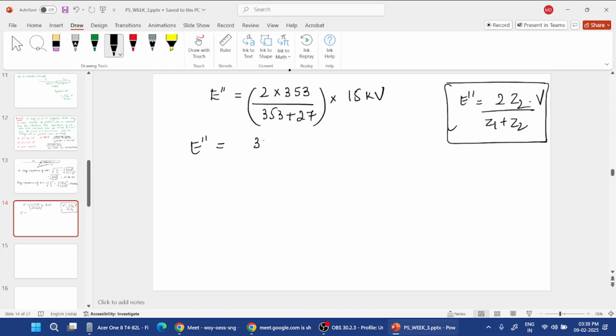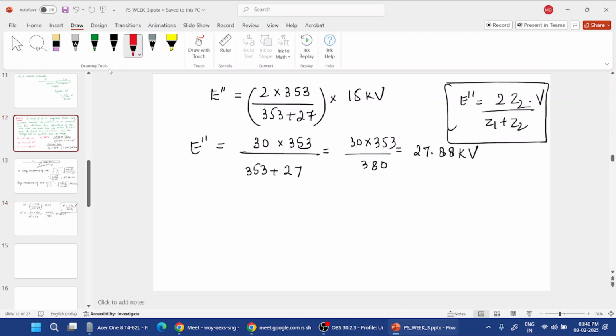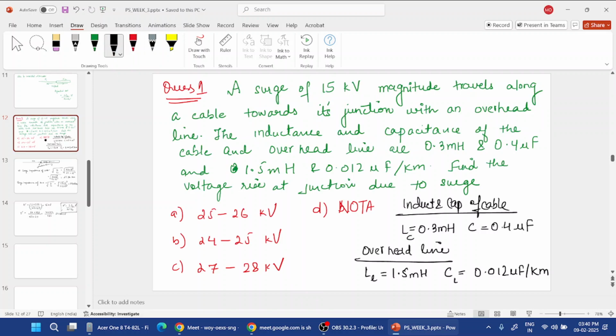So if we solve it, it comes out to be 30 into 353 divided by 353 plus 27, which is 30 into 353 divided by 380. So it comes out to be 27.88 kV. So the voltage rise at the junction is equal to 27.88 kV. Based on that, the correct answer is option C.